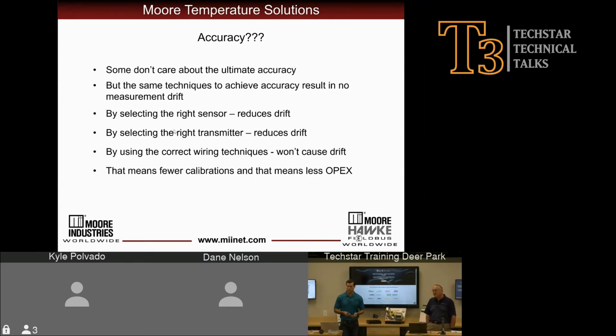So we can reduce drift by selecting the right transmitter or selecting the right sensor, using correct wiring techniques. All of these things that reduce drift also mean fewer calibrations for you, which is less operating expenses. So it saves you money just by improving accuracy and eliminating the drift in your temperature measurements.